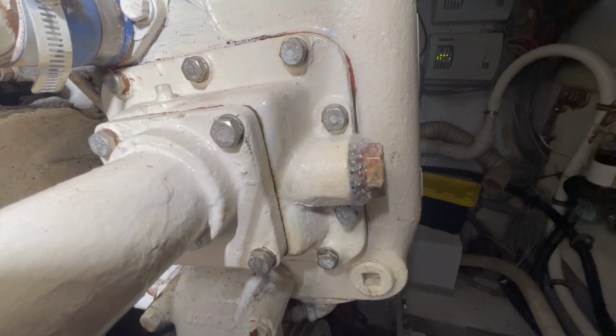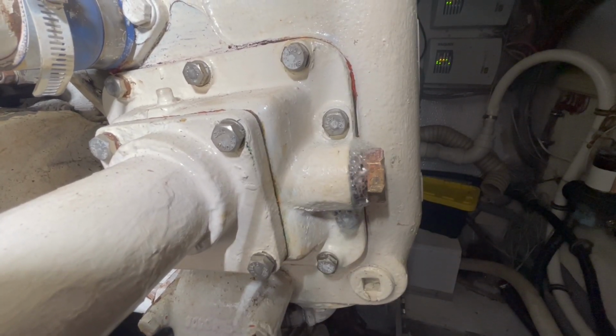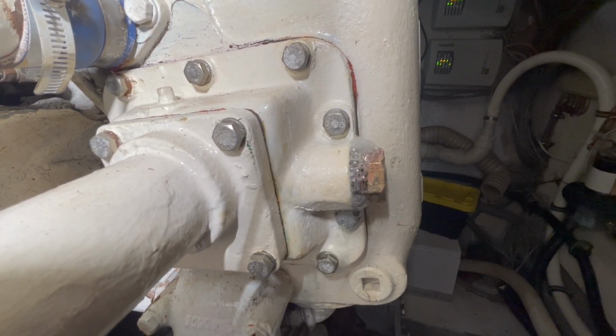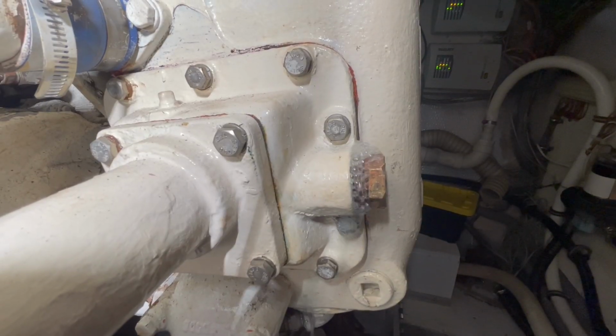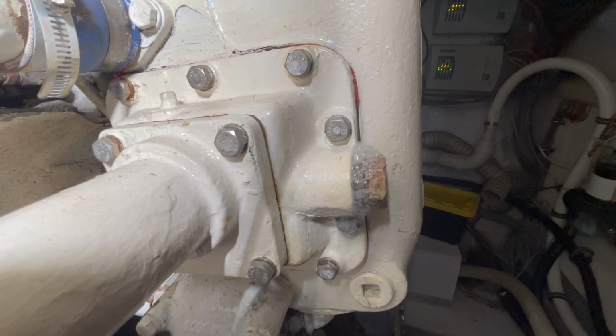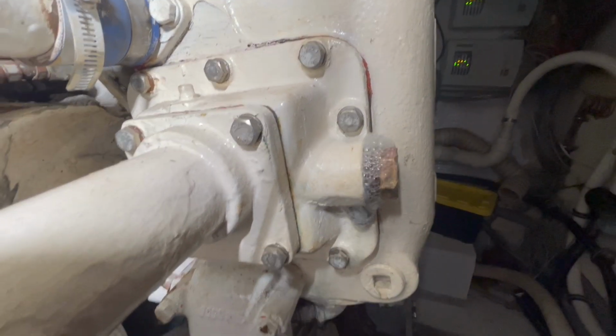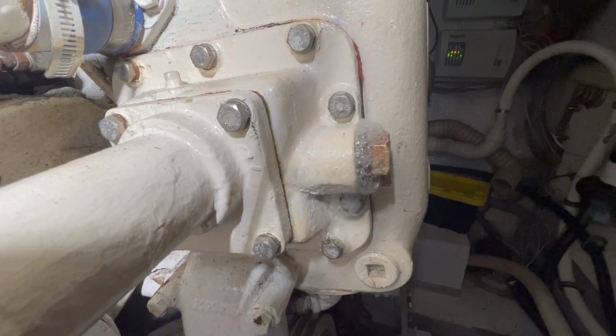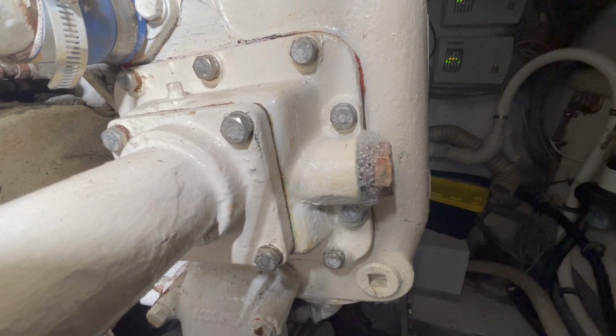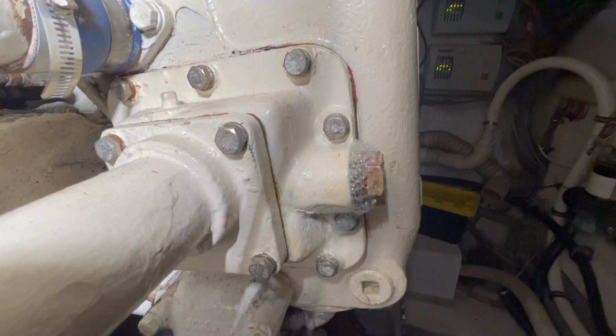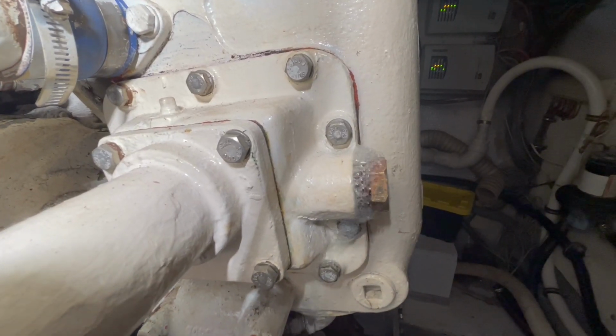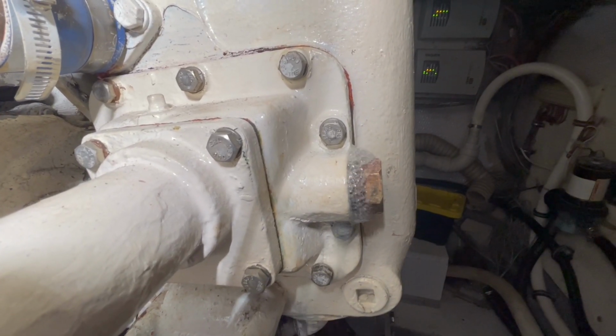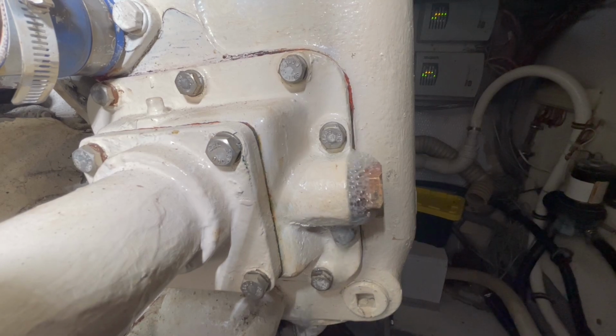But I did this on the other side when I did it, and I found that it went almost to the top of the heat exchanger with the cleaning. When you don't do that, it seems like it only cleans the bottom third or half of the heat exchanger. So you want to be sure you bleed all that air out of your heat exchanger, out of your tank here.